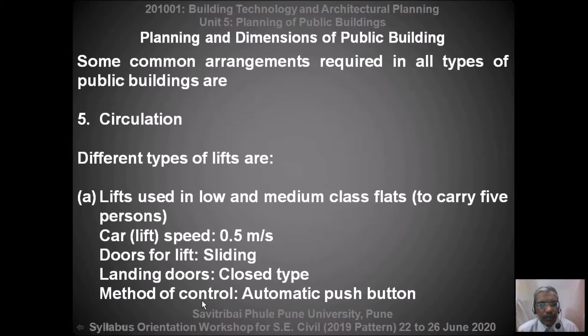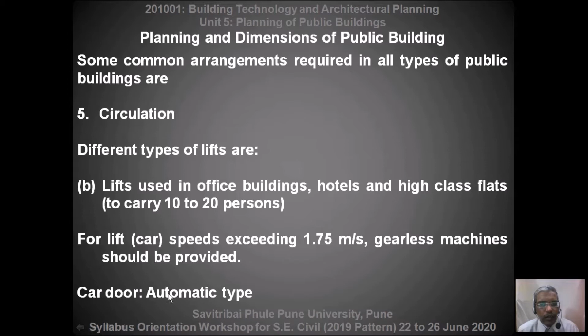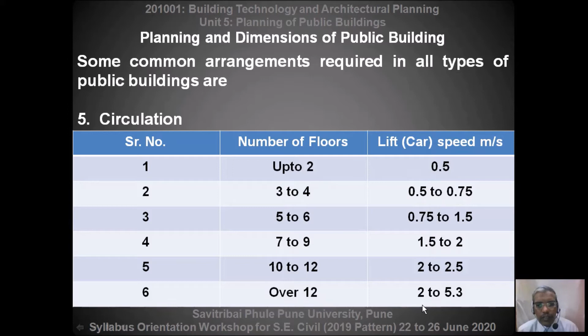Next, lift you can consider as the lift used in the office building, hotels and high class flat to carry 10 to 20 persons. For lift car speed exceeding 1.75 meter per second, the gearless machines should be provided. The car door, the lift door should be automatic type. So for the vertical circulation, number of floors up to 2 floor, the lift speed should be 0.5 meter per second, 3 to 4, 0.5 to 0.75, like this. Over 12 floors 2 to 5.3 meter per second.